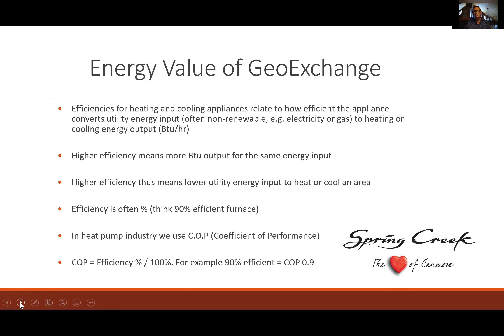So how does this work, the energy value of GeoExchange? Well, the green line down there is our loop, our field, where we have that renewable energy, where we take the cold fluid and we reheat it back to our normal ground temperature. We compress that to whatever temperature we generally require, generally 110 degrees Fahrenheit, and then we use that warmth and we blow that into our building. We are using electricity to work that compressor. And generally for heat pumps, we end up with a coefficient of 4, that for every unit of energy we put into the system, we get 4 units of energy out.